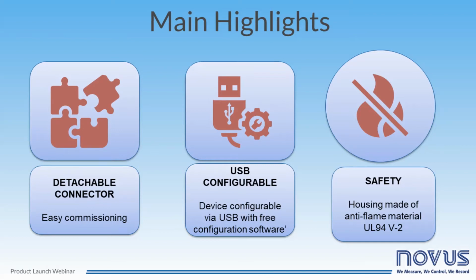And the last key advantage is the safety offered by the injected material of the housing. The housing is made of anti-flame material. We use polycarbonate, which is certified UL 94 V2. This material is flame retardant against the occurrence of an ignition in the electrical panel.